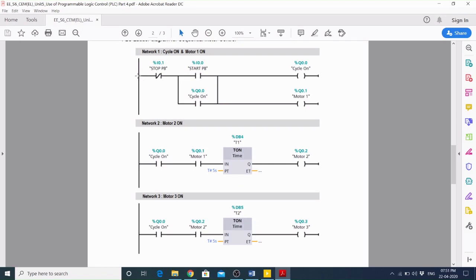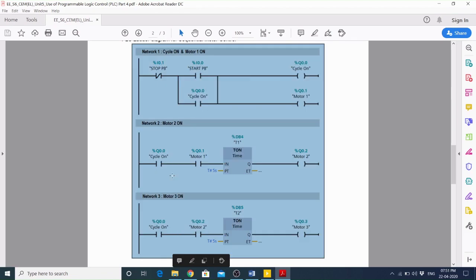Here you can see that power will flow through the stop push button because it is NC type, so current will be able to flow through this. Current will not be able to flow through the start push button unless the momentary type push button is pressed. When the push button is pressed, the current will be able to flow through this path and the main contactor coil will energize. When the main contactor coil is energized, at that same time the auxiliary contacts - this one, this one, and this one - will also energize.